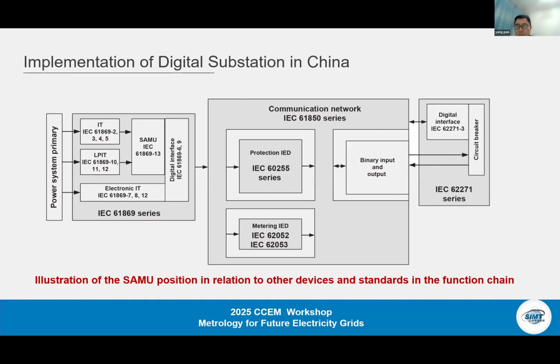So this diagram illustrates a typical digital substation architecture. During more than 10 years of operation in China, the prevalent approach for implementing IEC 61850-based digital substations utilizes traditional instrument transformers in conjunction with standalone merging units. While early implementations explored digital output electronic instrument transformers, this approach is currently not widely adopted. The instability of optical electronic transformers, which are susceptible to temperature or vibration, may be a primary contributing factor. The favored architecture relies on the standalone merging units to convert the analog signals from conventional instrument transformers into digital sampled values.